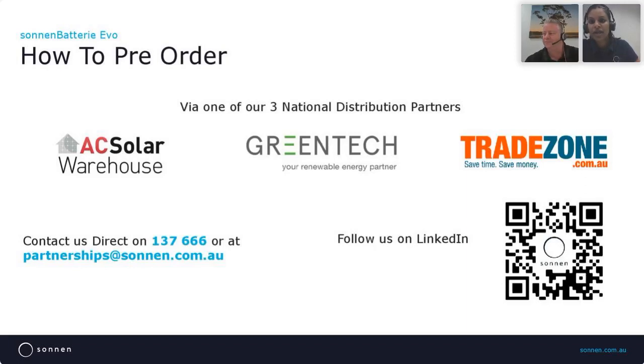We have a question around whether the battery can be installed outside without the special casing. Yep, that's the beauty of the sonnenBatterie Evo - one of the prerequisites of the design is that the cabinet it comes in is an IP56 rated cabinet. So compared to previous Sonnen modules, there's no additional outdoor cabinet required other than the main cabinet the sonnenBatterie Evo is part of.